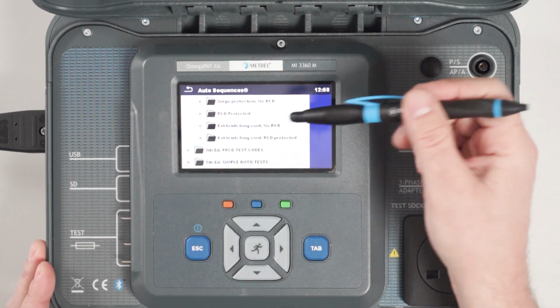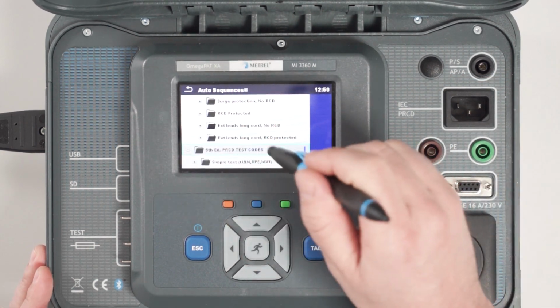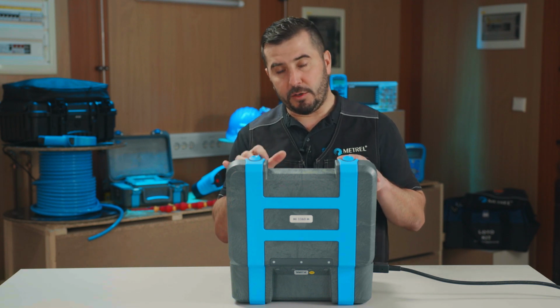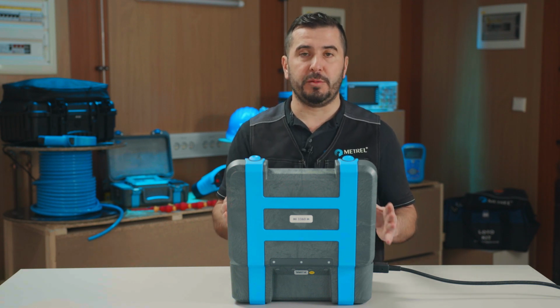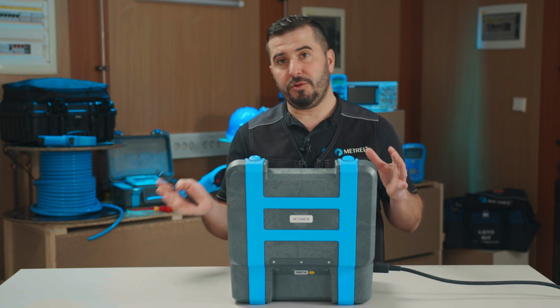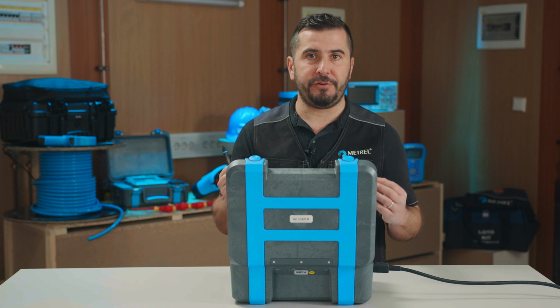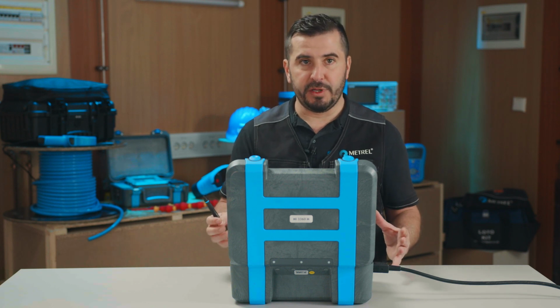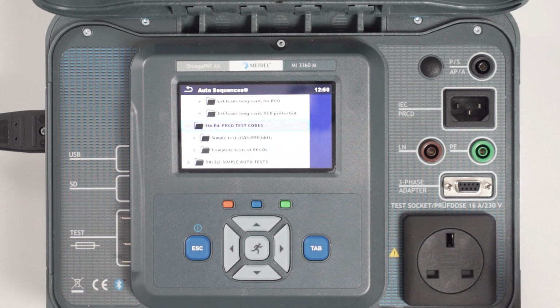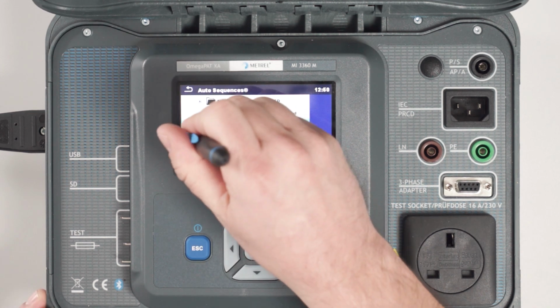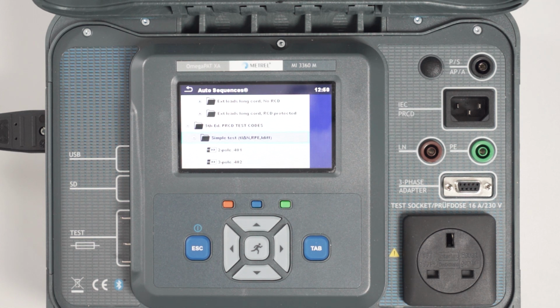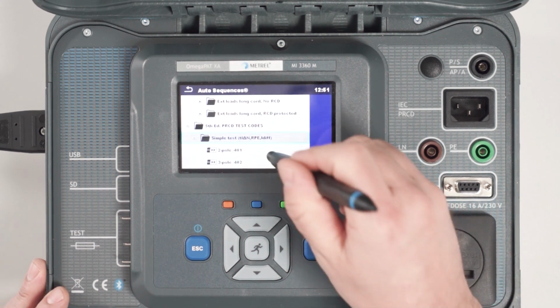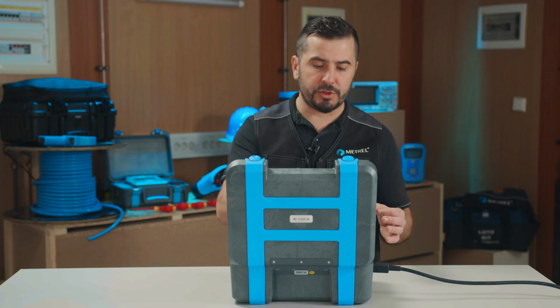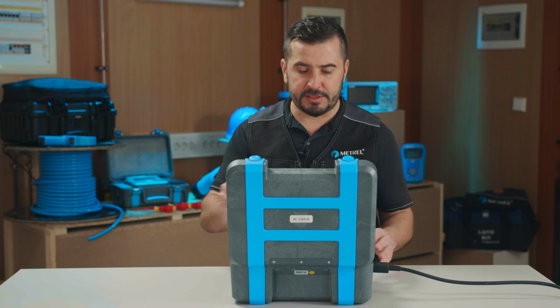Then we have a special chapter, or special group of auto sequences, with only auto sequences for special portable RCD devices. On the market we can find some manufacturers of portable RCD equipment who are approaching this in a different way, so that the portable RCDs are intelligent and can also detect problems of your mains installation, and therefore they have to be tested accordingly. So inside here are different auto sequences designed for these special accessories.